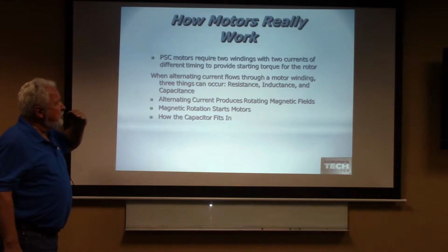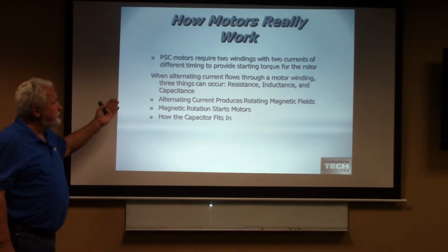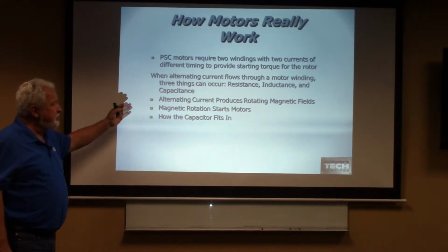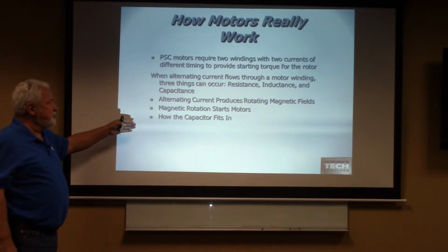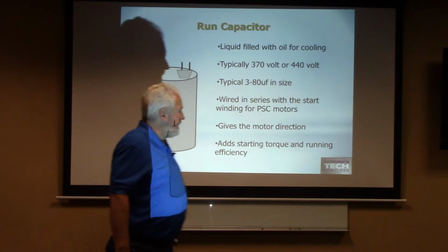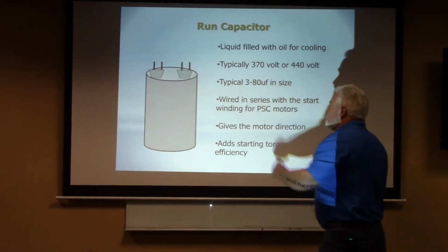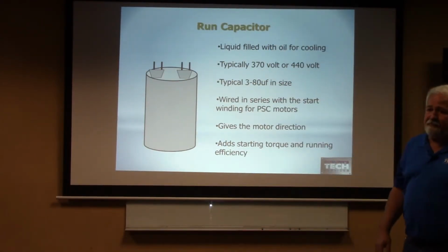When alternating current flows through a motor winding, 3 things can occur: resistance, inductance, and capacitance. Alternating current produces rotating magnetic fields. Magnetic rotation starts the motor, and let's figure out how that capacitor fits in. Here's our run capacitor. It's liquid filled. It's liquid filled with oil to keep it cool.